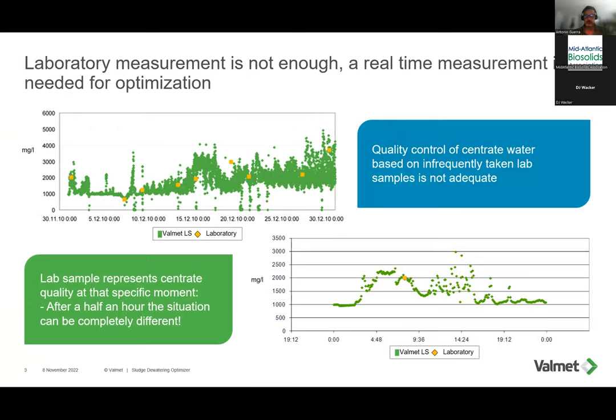Historically, or typically, the way it's done in most cases is the operator will grab a lab sample. You can see that bottom graph. A lab sample is taken at a certain point in time, that is the orange dot. So the operator is trying to control this process based on that moment in time. Well, as we know, that one point in time is not indicative of what happens over a longer period of time. That process variable will vary, solids concentration will vary. So if we can have measurements that allow us to control the process in real time, as opposed to that one moment in time, that is definitely a way to be a lot more efficient.